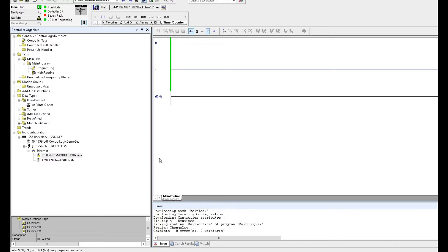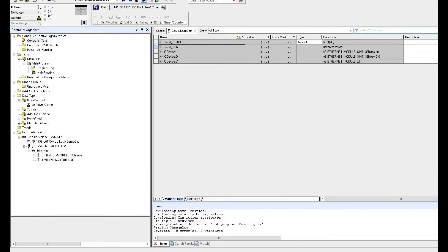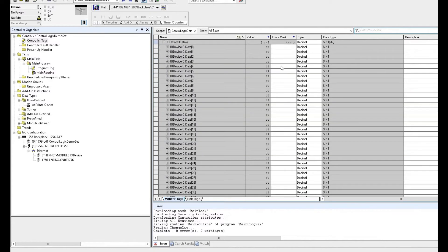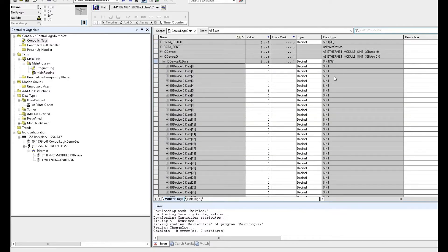The background information is that this project uses a CompactLogix or ControlLogix controller. The device is one remote device. The EDS file was created using a generic EDS file. This generic module is named IODevice, with an IP address and assembly instance — all based on the manual from that Ethernet IP device. In the controller tag, it creates this structure, and all the output bytes are byte-based. We set 32 bytes here. No problem.